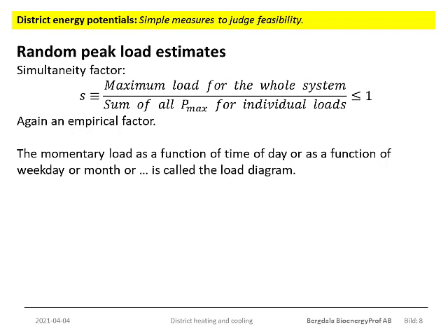Plotting the momentary demands as a function of linear time will result in what we call a load diagram. This will help in planning since it will give you an idea of the momentary loads. The philosophy behind district energy is to supply a large number of customers. It goes without saying that what I'm talking about now are individual random peaks, like the peak demand during mornings when individuals have their wake-up morning shower. These things will be clear from the load diagram.